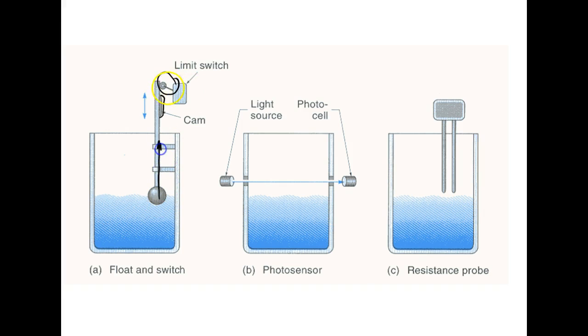When the float gets up to a certain place, it rides over that cam and turns it off. Y'all got an ice maker in your refrigerator? It's almost this exact same thing. You've got that little wiper, and when it raises it disables the limit switch. When you feed ice off it, the level drops down, that metal wire drops down, and it tells it to feed more water or to eject the ice. Everything after that is timed.